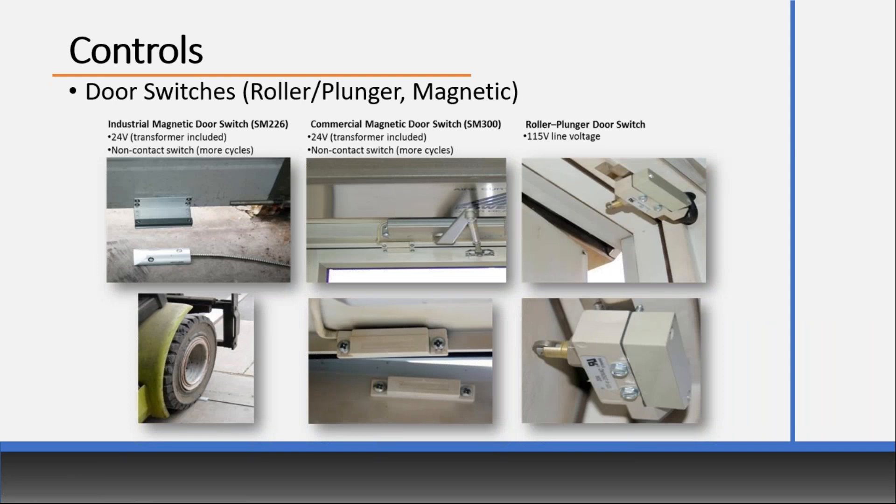Getting into controls: 99% of air curtains we ship are supplied with a door switch. Unfortunately, what's become standard in the industry is the roller plunger door switch — it's big, it's bulky, and the roller arm is the most likely thing to break. I try to discourage engineers from using it because there are so many better options. Our preferred industrial door switch is low voltage, includes a low voltage transformer, is much more durable, and fork trucks can run over it. Our commercial SM300 is much smaller and aesthetically pleasing. There are also door switches that recess into door frames and wobble switches — many options beyond the roller plunger.